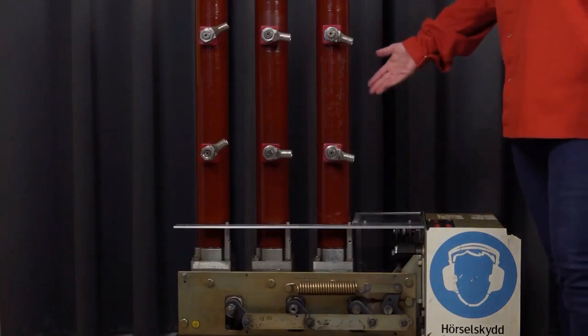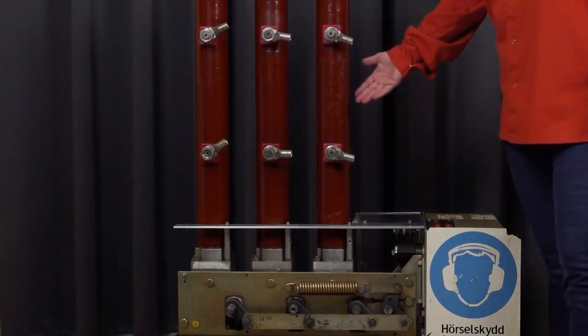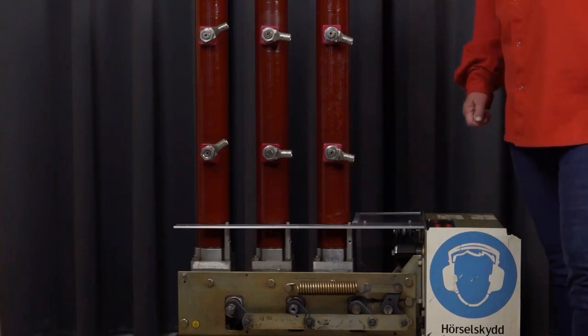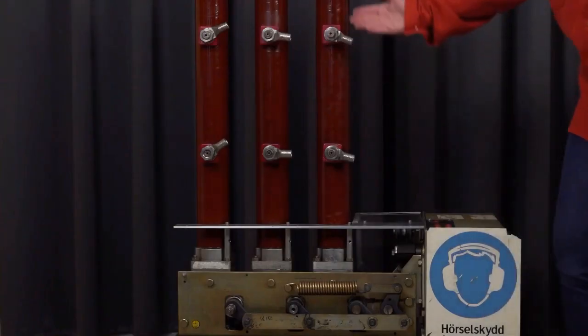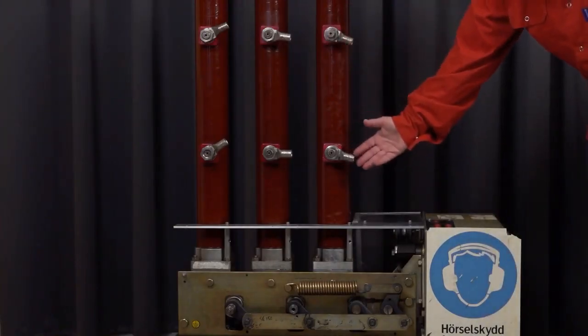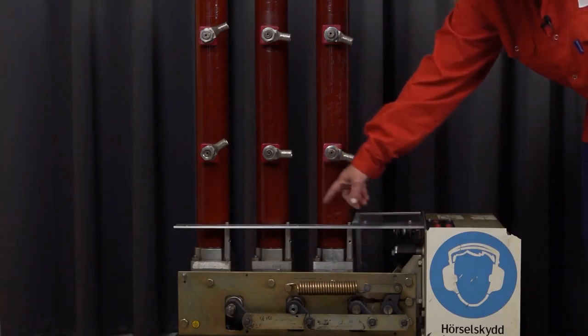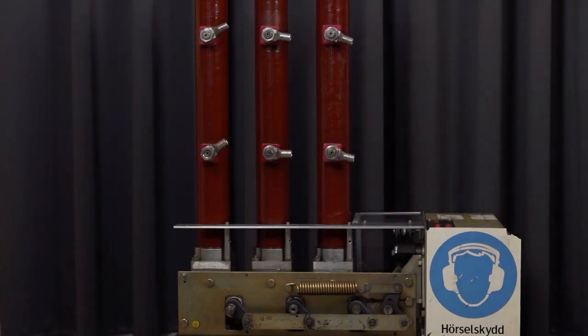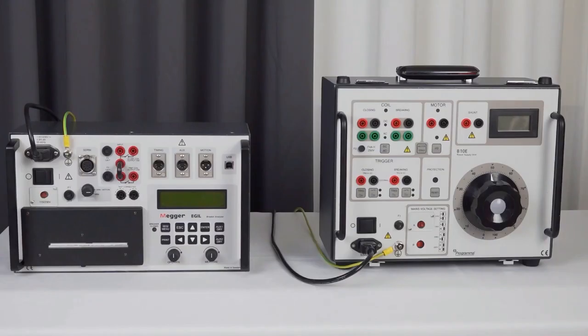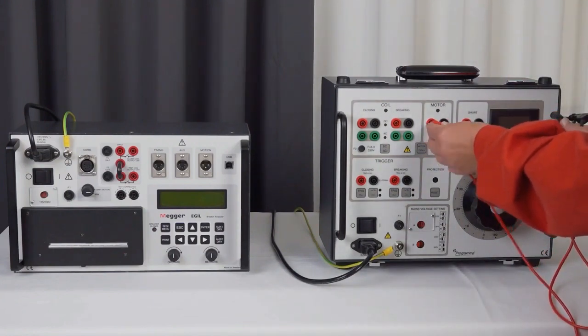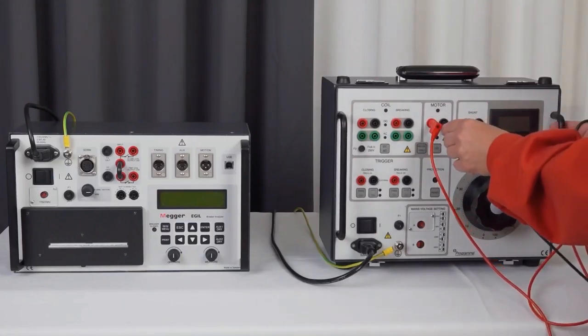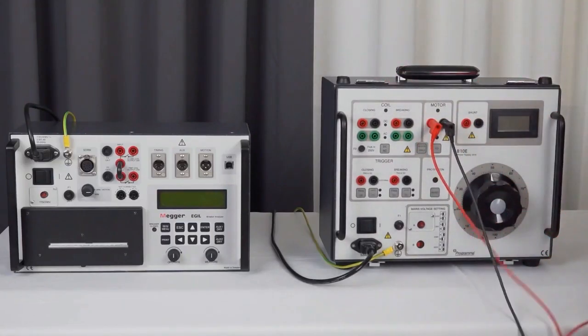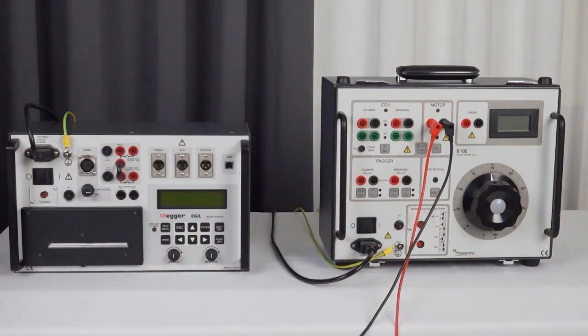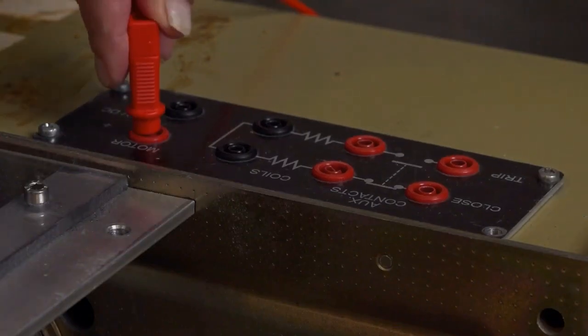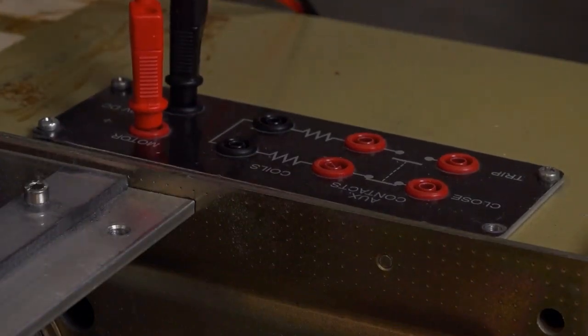We're going to measure on the circuit breaker Sacher. It's a 12 kV medium voltage breaker. It has 3 phases, the upper and the lower contacts. It has a motor mechanism, a common mechanism for all 3 phases. I'll start with connecting the plus and minus of the motor charging on the instrument. Plus and minus. I connect plus and minus for the motor on the object.